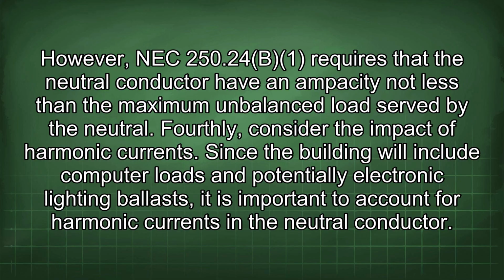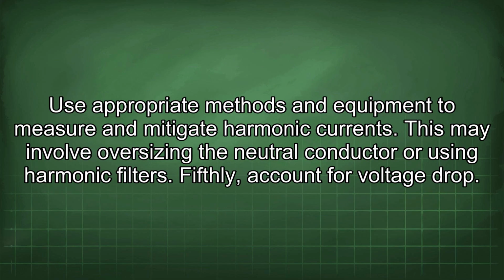Fourthly, consider the impact of harmonic currents. Since the building will include computer loads and potentially electronic lighting ballasts, it is important to account for harmonic currents in the neutral conductor. Use appropriate methods and equipment to measure and mitigate harmonic currents. This may involve oversizing the neutral conductor or using harmonic filters.